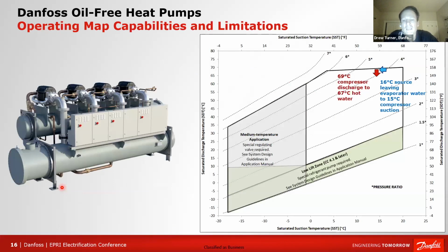And this just highlights, for a specific application, the combination of operating temperatures that you're going to operate at. So for a water-to-water heat pump, for a specific operating heat recovery temperature, and it's kind of hidden behind here right now, it's about 15 degrees Celsius coming into the evaporator or heat recovery temperature, and 69 degrees Celsius on the discharge coming from the compressor, which is at the upper end of our capability. But as you get into a more air-to-water heat pump application, you push down this line. So our technology is optimized today, even with the higher lift capability, for the water-to-water heat pumps, and it would be trading off capability for the air-to-water heat pumps. So it's best, with the expanded capability of this technology, to focus on water-to-water heat pumps.